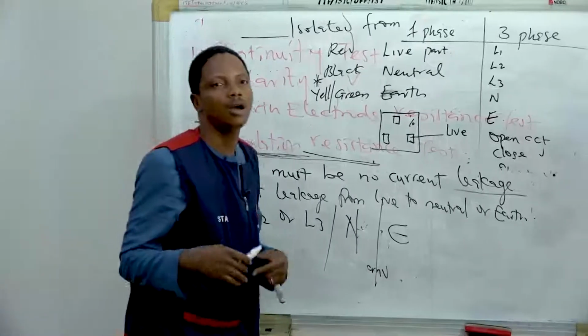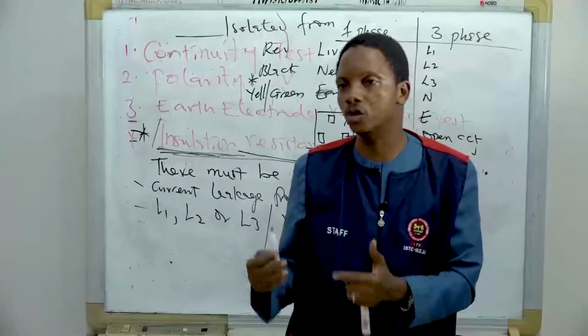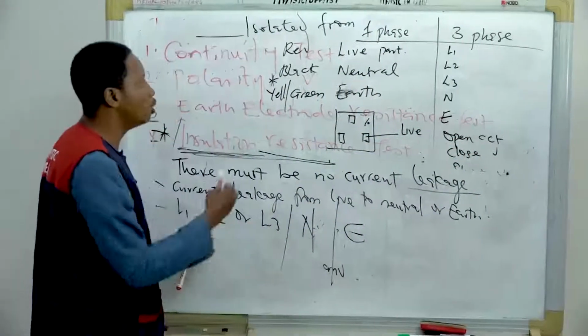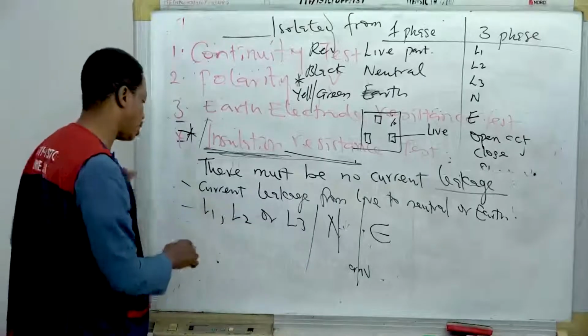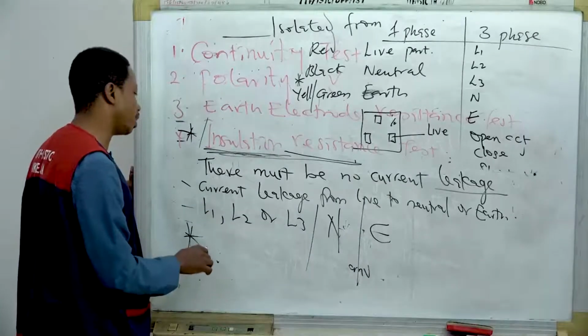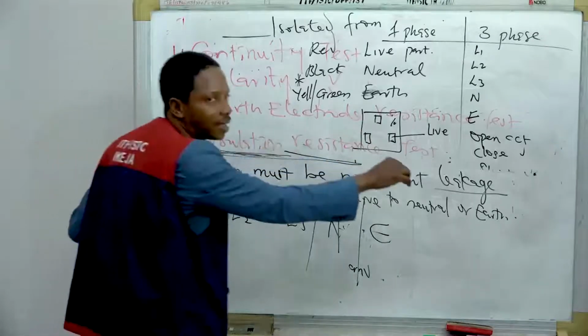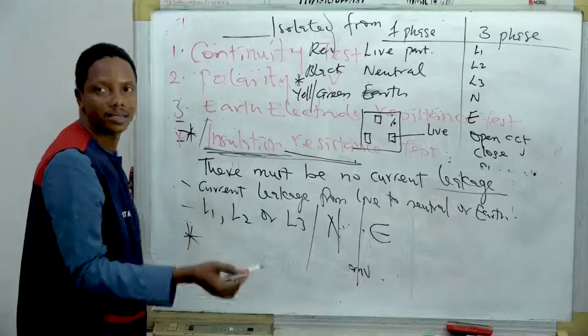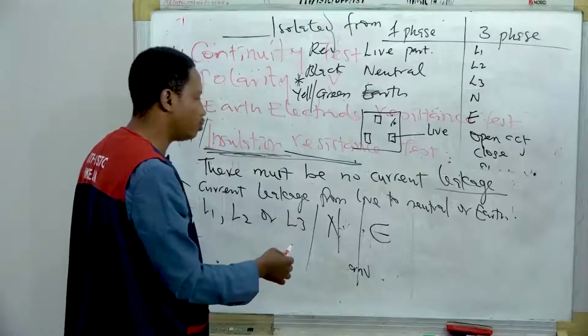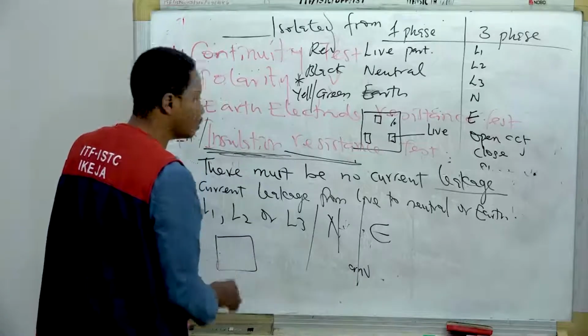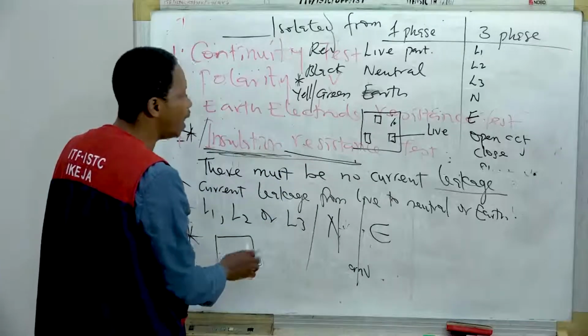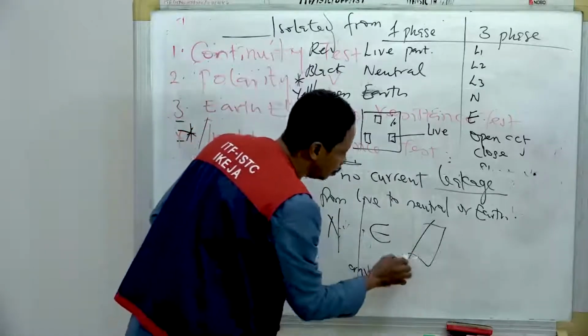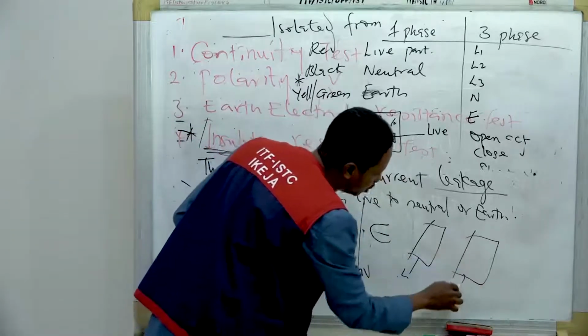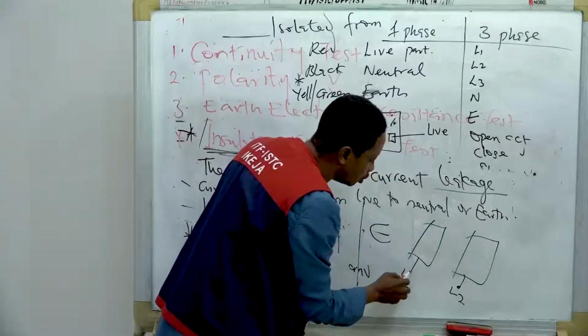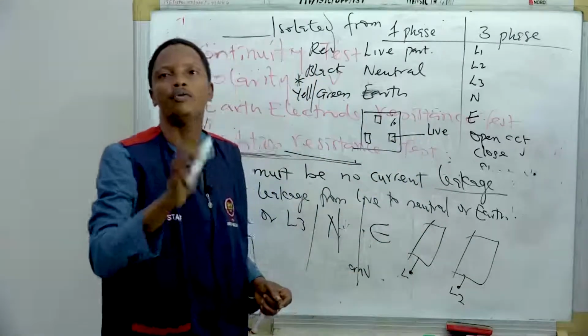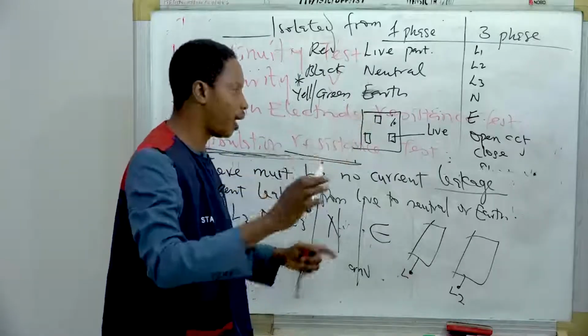So in practical class, I'm going to demonstrate this with the use of an ohmmeter. Not only the ohmmeter do we use to carry out insulation resistance test. Another meter that can be used to carry out insulation resistance test is what we call an insulation resistance tester, or megger tester. So we also use this. And how does it work? Let me use the megger tester to explain. So when there is no leakage, when you carry out this cable, line 1, and then assuming this line 2. Now, carrying out insulation resistance, all circuits are off, all loads removed, and the main supply is isolated.